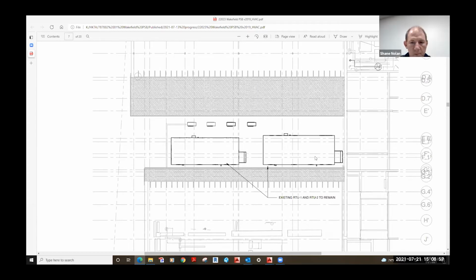Coming out of schematic design, when we went through the whole VE process, my understanding was we had to replace rooftop unit number 2 from a 10,000 CFM to I think 17,000 for the capacity. We were going to maintain or retain rooftop unit 1, 3, and the air handling unit, but we were going to put those in as alternates, in hope that some additional funding would become available, because these units may last another year, 5 years, possibly 10 years, but certainly not another 25 years.